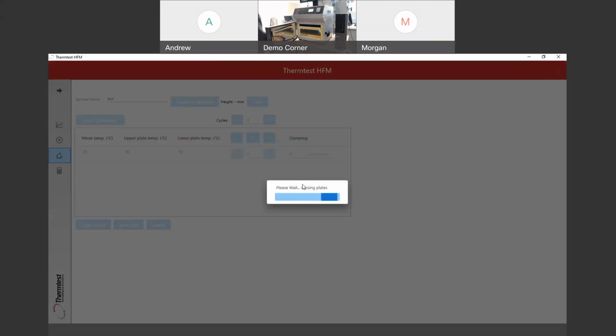Oh, I didn't put that there. The only thing that I'm testing is polyurethane foam. So you'll never do that then. No. And do you think that's the right temperature as far as the 30 upper and 10 lower? Again, for what you're describing, I would do a 20-degree delta at whatever mean temperature you want to do. Okay. I like 20. And put the highest temperature on the top.